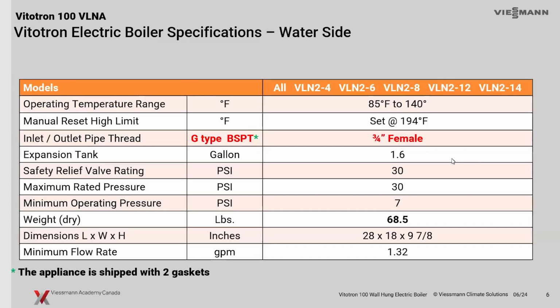It comes with a 30 PSI relief valve. Just kind of jumped the gun there a bit. Sorry about that. There is a minimum operating pressure. It does have a pressure sensor in it. We'll have a look at that at 7 PSI. And a pretty small boiler, like I said, 28 by 18 by 9 and 7/8 deep. So it fits in a very small spot. And, real estate being what it is nowadays, having that small footprint is very advantageous.